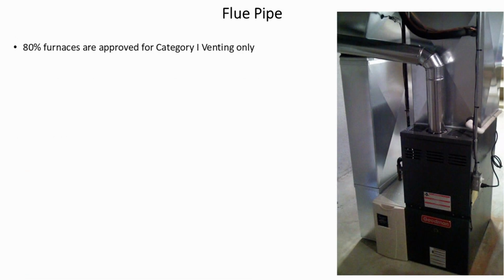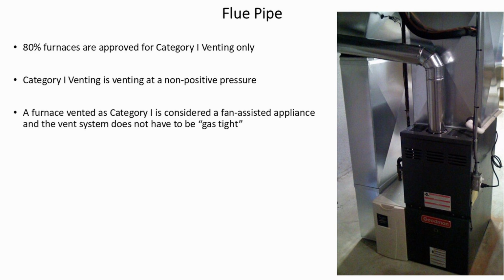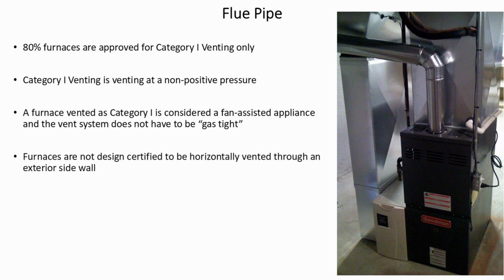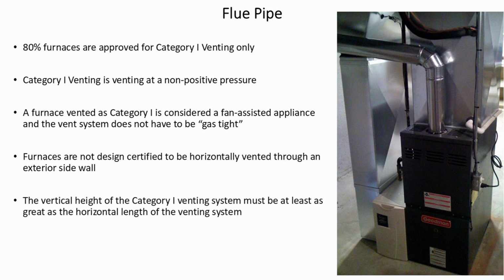80% gas furnaces are approved for Category 1 venting only. Category 1 venting is venting at a non-positive pressure. A furnace vented as Category 1 is considered a fan-assisted appliance, and the vent does not have to be gas-tight. Furnaces are not design certified to be horizontally vented through an exterior sidewall. The vertical height of the Category 1 venting system must be at least as great as the horizontal length of the venting system.